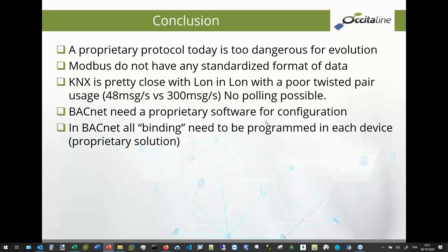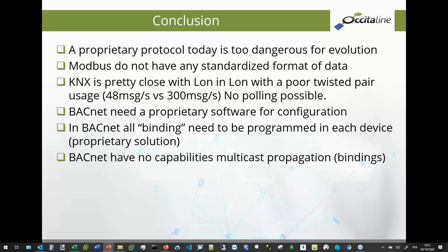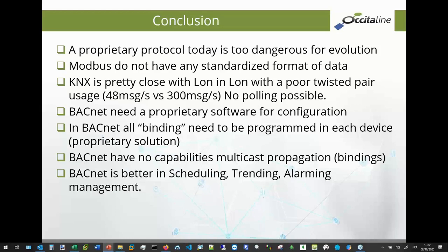In BACnet, the connection, the binding, needs to be programmed in each device. Why? Because the connection between two objects is not supported by the protocol today. All master-slave connections between two devices are proprietary solutions. Each manufacturer has invented its own solution for creating that. If you want something more open, you use a BACnet device and read and write some information like the SCADA. You centralize the connection between the main PLC and the different devices on the field.